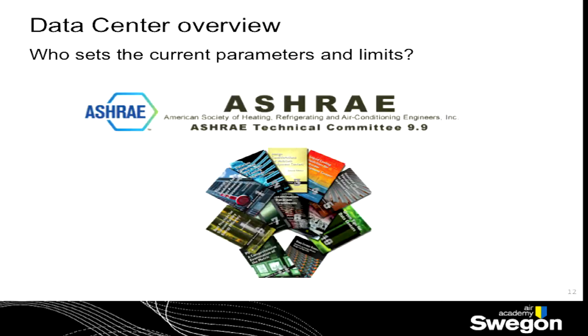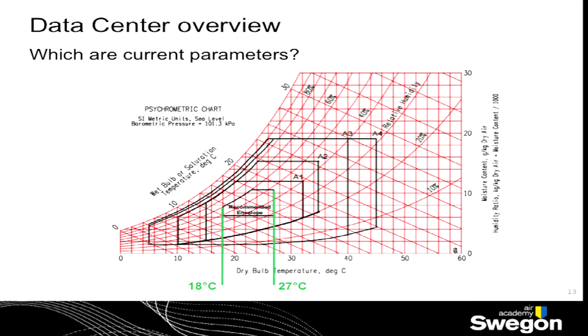Let's have a look at the psychrometric diagram. What does it mean? It means that this is the recommended envelope. So between 18 degrees and 27 degrees, we are right. With the current technology for servers, these are absolutely recommended temperatures. So if we have temperatures between 18 and 27 with a humidity level that goes from, let's say, 30% to maximum 60%, we are in a right position in which the server works in the proper way.